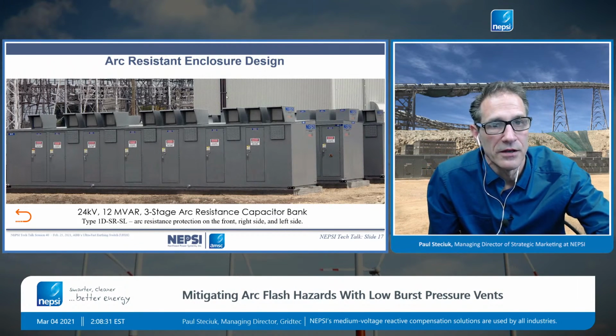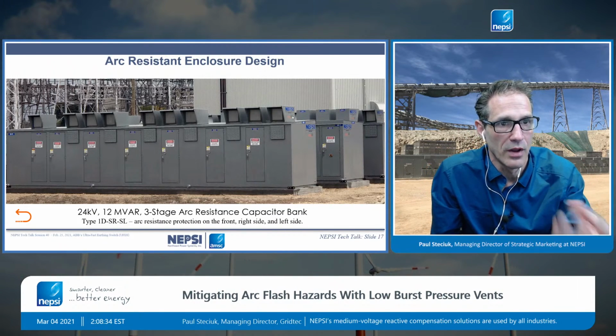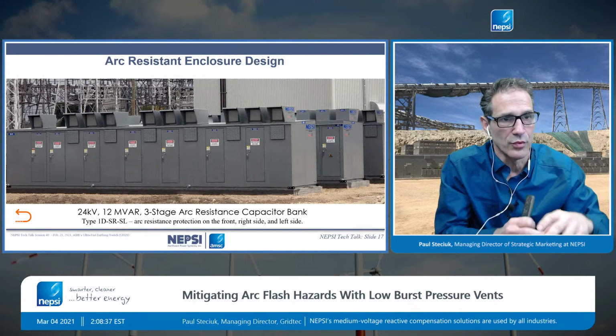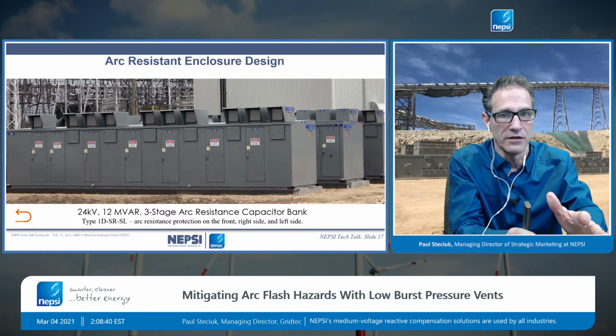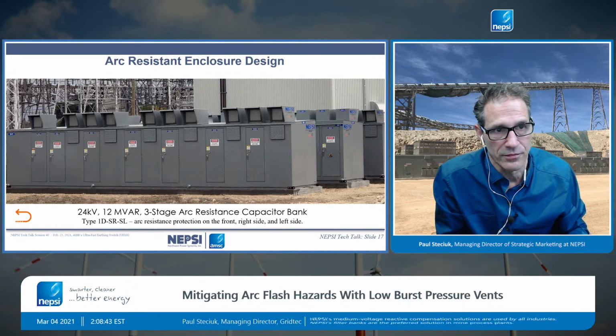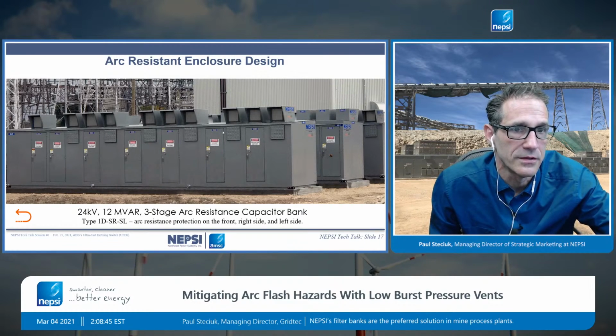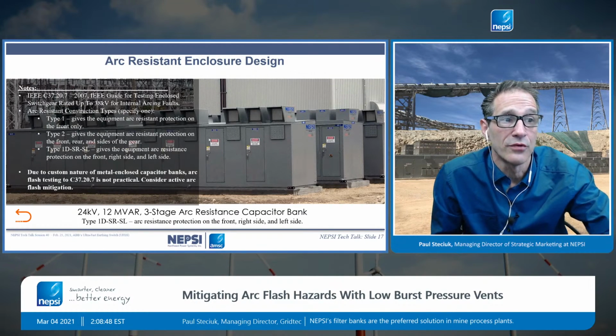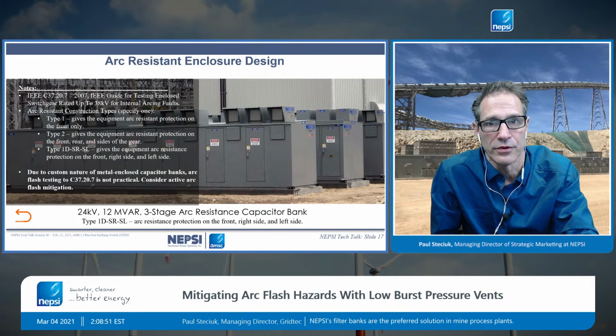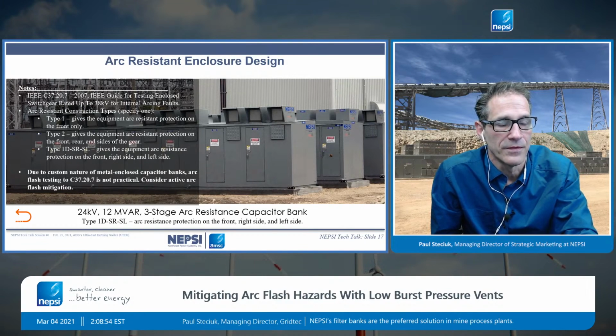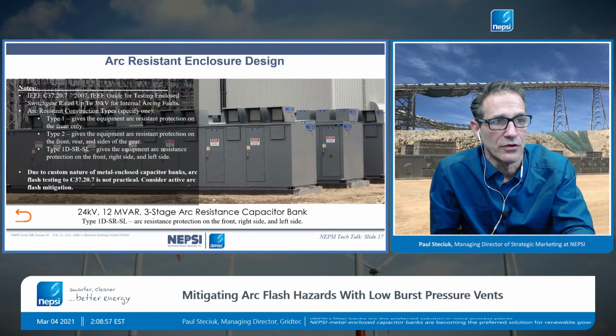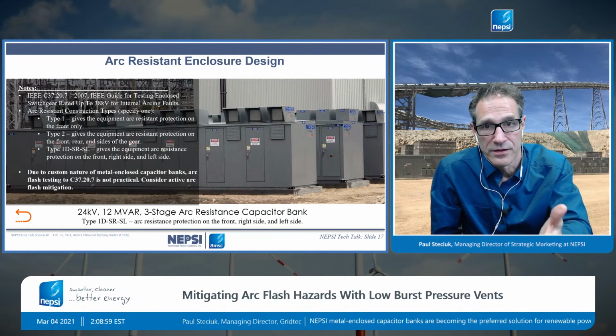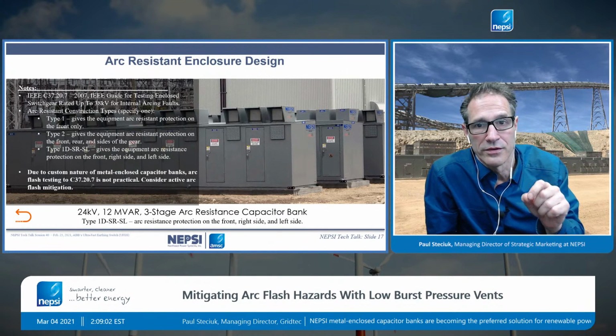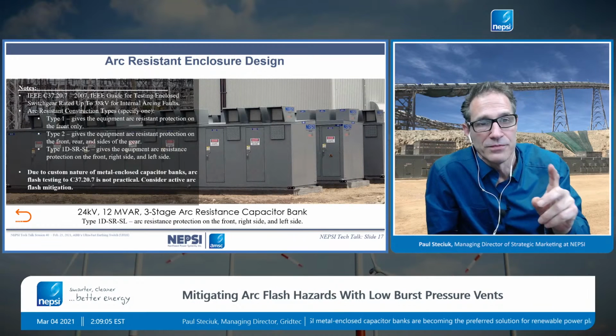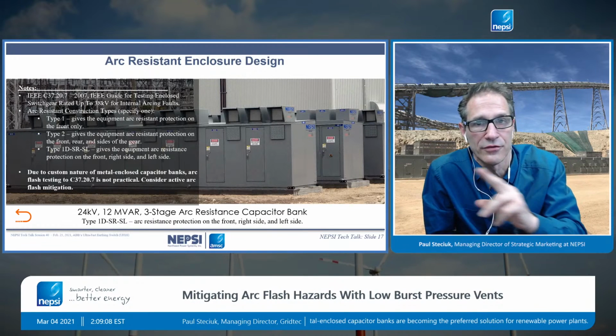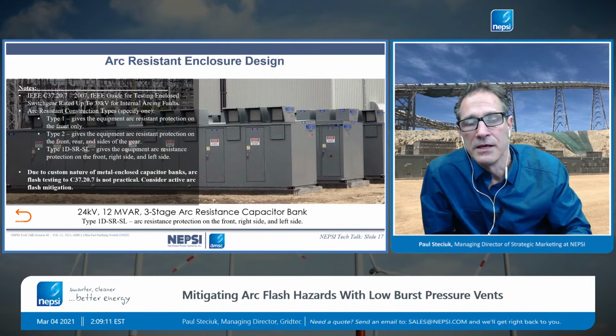And in this design here, we still have louvers and things that can block the release of pressure. So the objective here is we want a clear opening. We want the pressure to leave. We don't want a door to get blown off into somebody. Okay, so there are some standards in the United States. C37.20.7 is a testing standard, and there's different types of arc flash enclosures, a type 1, a type 2, and in this case, that enclosure you're looking at here is a type 1D SRSL, which means that we can stand on certain sides of the equipment, but not on all sides of the equipment.